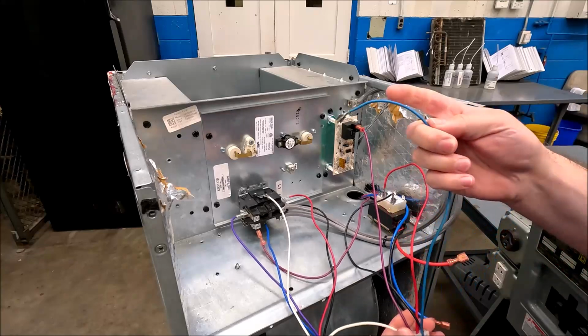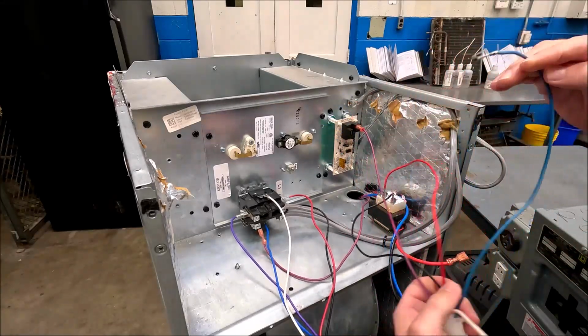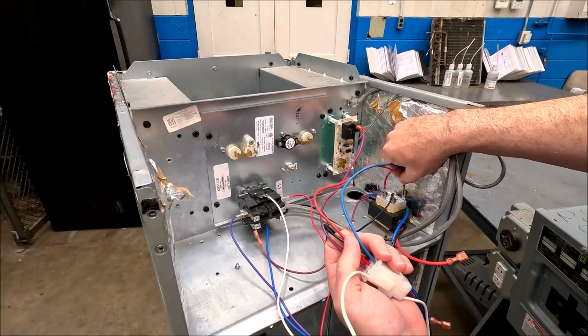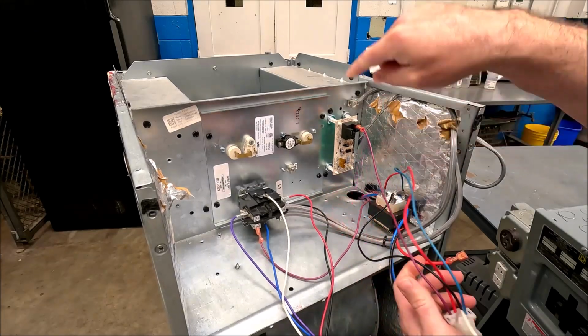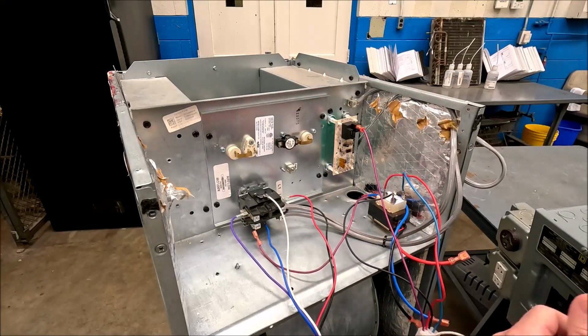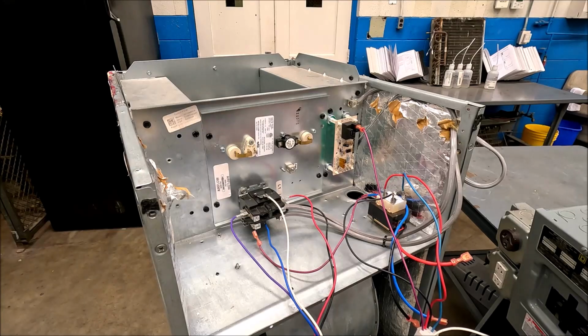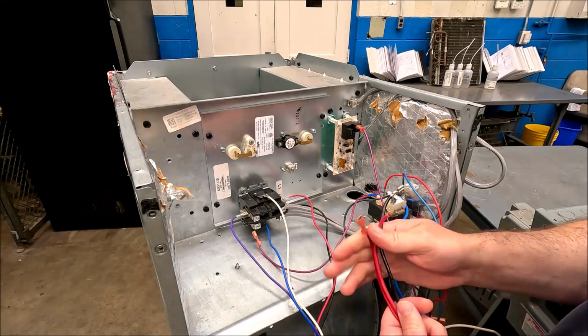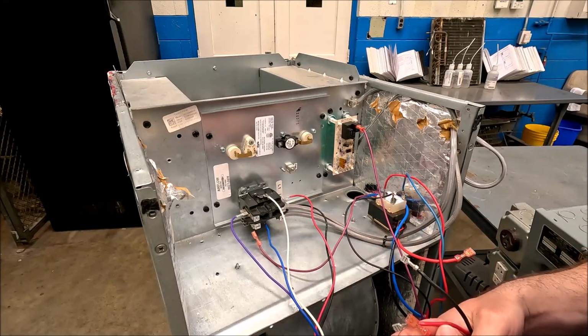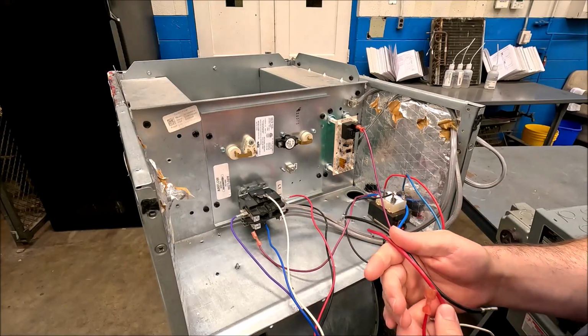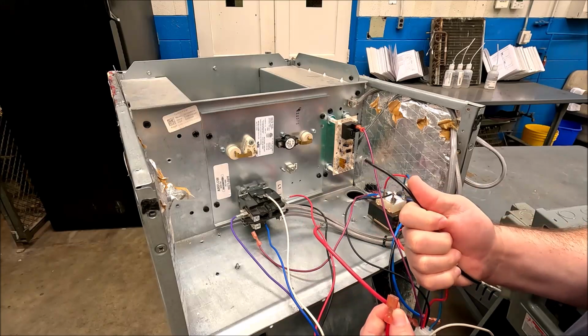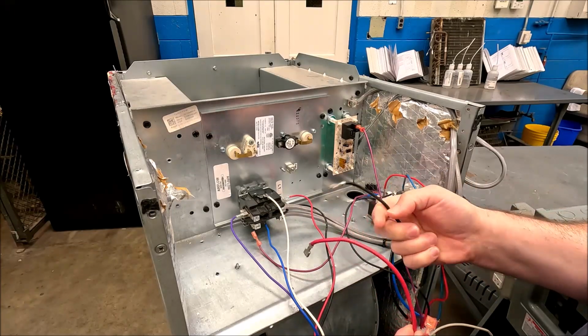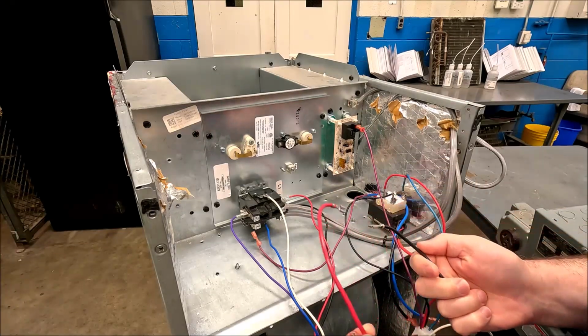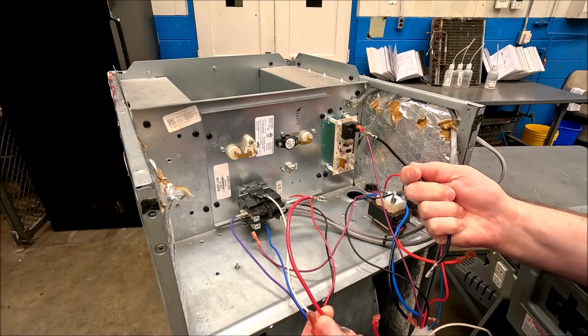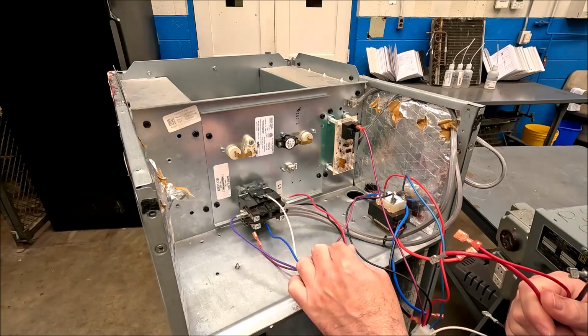And now I've got this 24 common wire right here. This is how the heat relay gets 24 volt common back to the transformer. So that's both my plugs. Okay, if I did the heat strips, I've got 3 high voltage wires here. Instead of 2 black wires for the heat strip, the high amperage part, we're looking at like a 12 gauge wire here. I swapped one of the black ones out for a red one just to kind of follow suit with them.